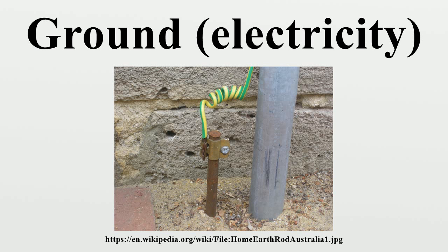Buried grounding electrodes are used to make the connection to the earth. The site of these electrodes must be chosen carefully to prevent electrochemical corrosion on underground structures. A particular concern in design of electrical substations is earth potential rise. When very large fault currents are injected into the earth, the area around the point of injection may rise to a high potential with respect to distant points.